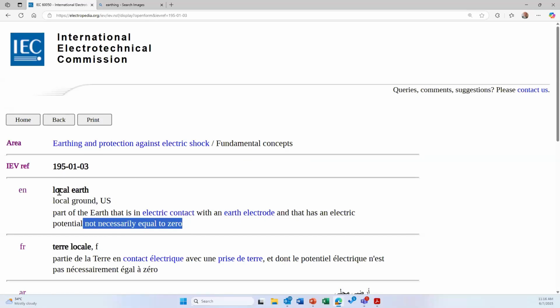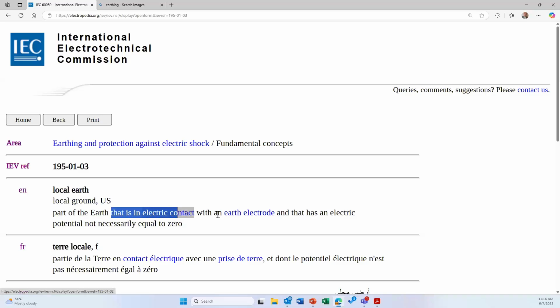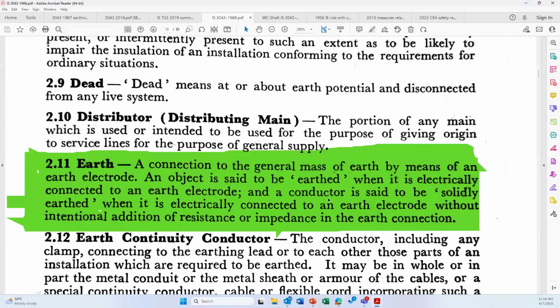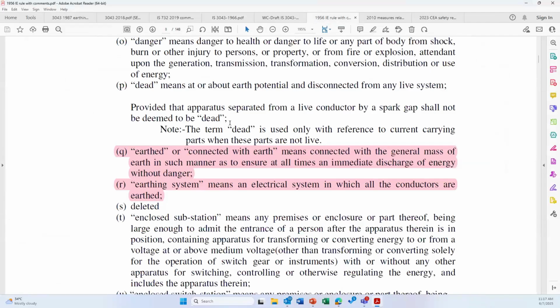Let's say, for example, you are in a room. What is the local earth in the room? It is an earth bus bar or an earth terminal in your room. And that particular earth bus bar in your room is in electric contact with an earth electrode, need not be directly. Somehow the earth bus bar in your room is connected to an earth electrode and need not have a potential equal to zero. So basically, fundamentally, there is a big change in the definition in recent years. Now, what has happened in our country was we were a little bit reluctant in changing our ideas. In most cases, we still use the definition of the 1956 IE Rules or the 2010 CEA regulations. As a result, whenever we talk about earthing, we were thinking about an earth electrode.